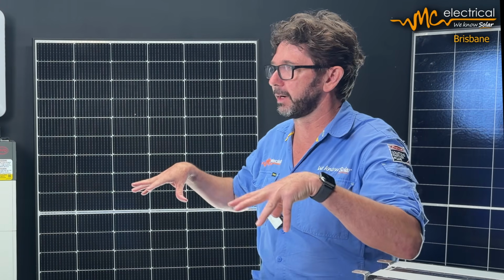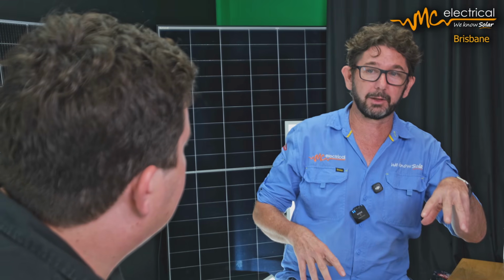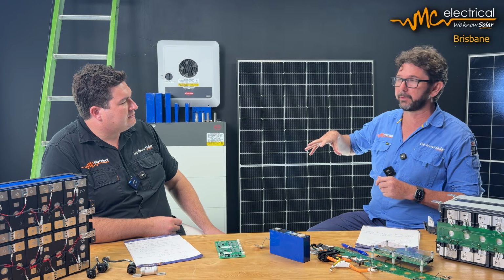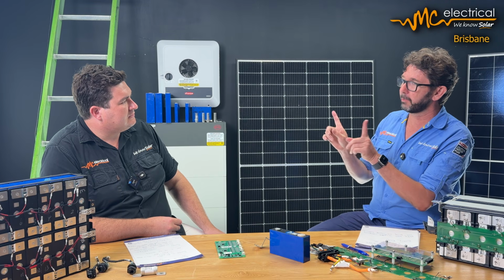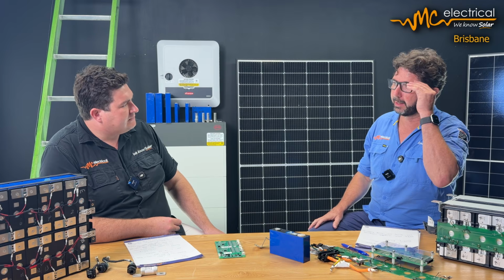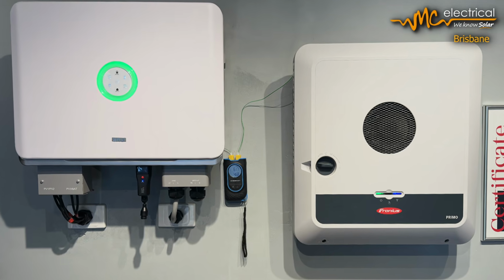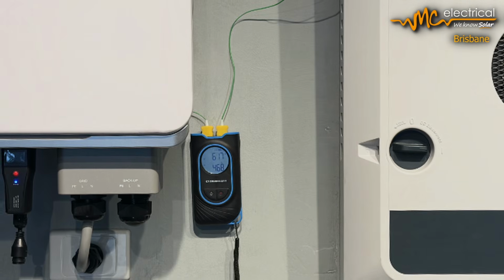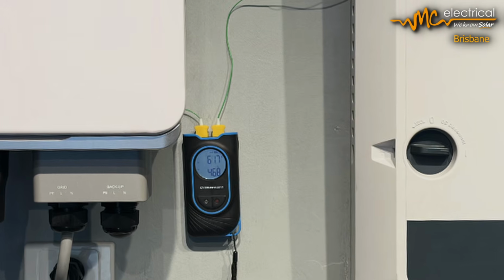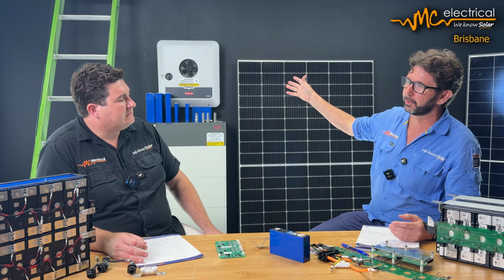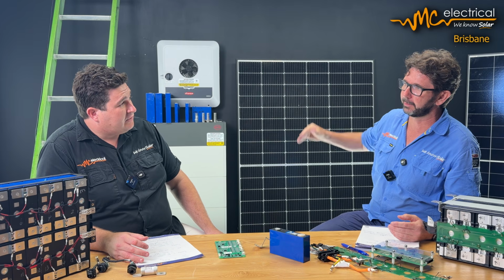So we were testing putting 8 kilowatts on the Fronius inverter, 8 kilowatts on the SAJ inverter, and put a temperature probe into both. We'll show that picture here. Even before the fan kicked in, the SAJ inverter was running 10 or 12 degrees hotter at really low light. Fronius didn't even have the fan kick in, and the SAJ is cooking.